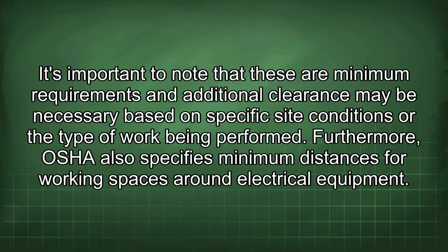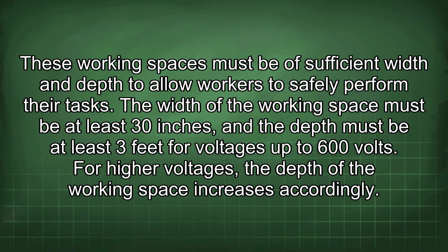Furthermore, OSHA also specifies minimum distances for working spaces around electrical equipment. These working spaces must be of sufficient width and depth to allow workers to safely perform their tasks. The width of the working space must be at least 30 inches, and the depth must be at least 3 feet for voltages up to 600 volts. For higher voltages, the depth of the working space increases accordingly.